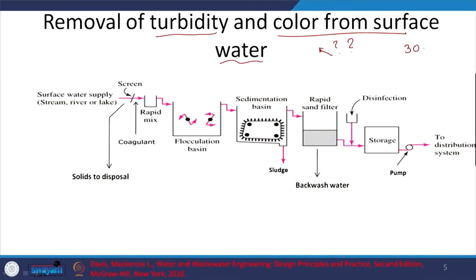One built earlier is based on the traditional technique, and we will look at that later. And the other one uses a wastewater treatment process based system to treat this surface water. Why is that? Because River Yamuna, depending on when you sample, is going to have high BOD, and maybe COD of 70, 80 milligram per liter, right? And here the issue is, the dissolved organic carbon will be around 8 to 9 to 12 milligram per liter. So it's under the category of sewage, let's say.